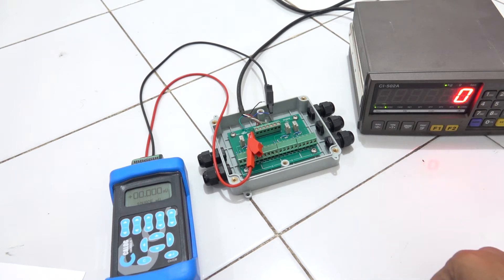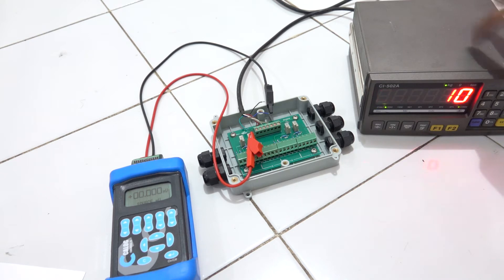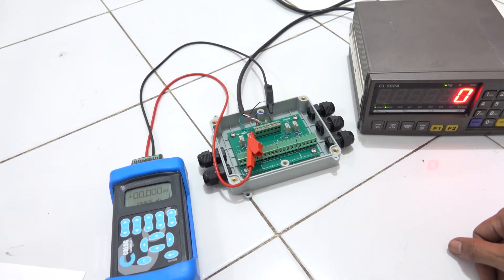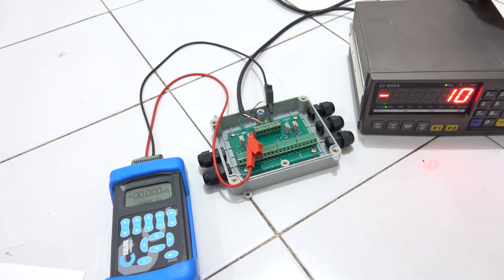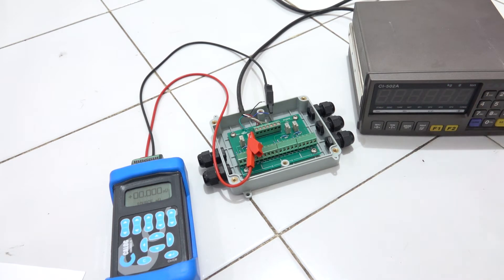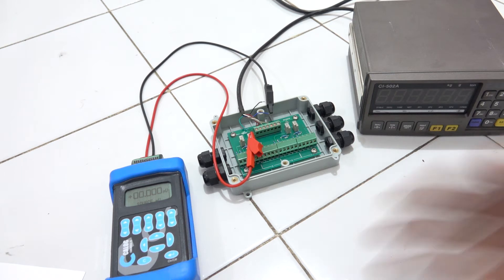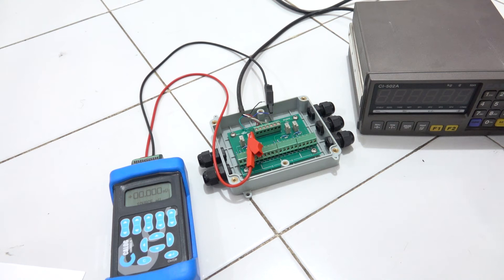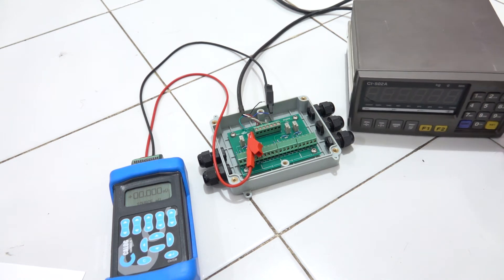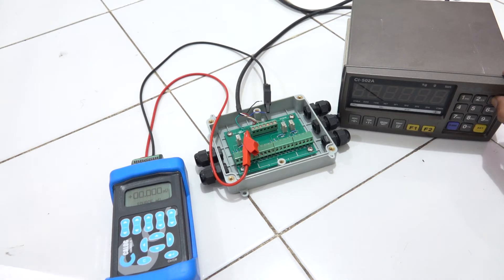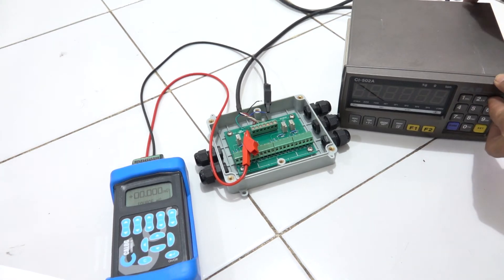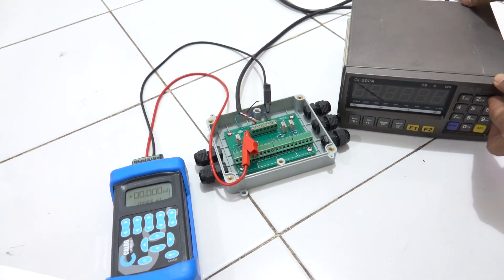First, we have to turn off this load cell indicator. Just turn it off. Based on the user manuals, when you do a calibration, you have to push number three here, then you turn it on. And you got this P1. Just press set and you have one until seven things that you have to set up to do the calibration.